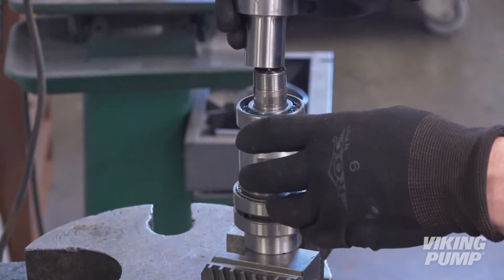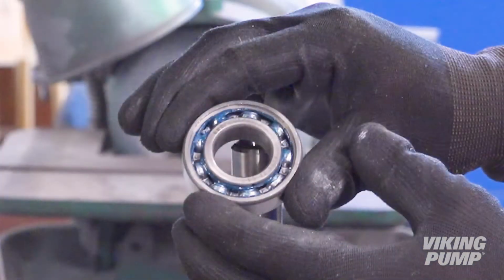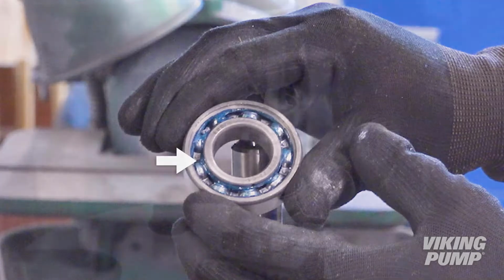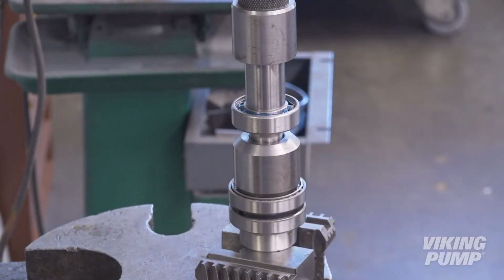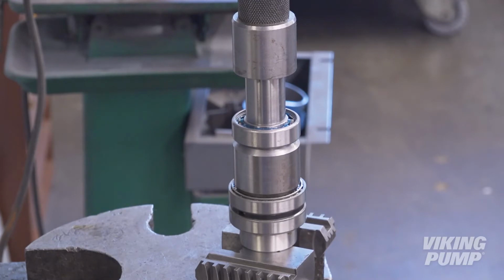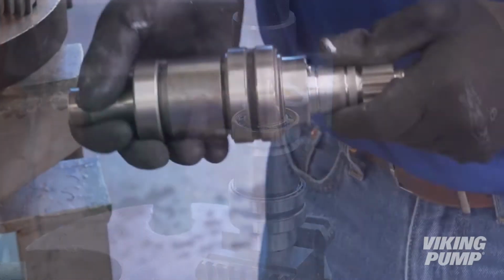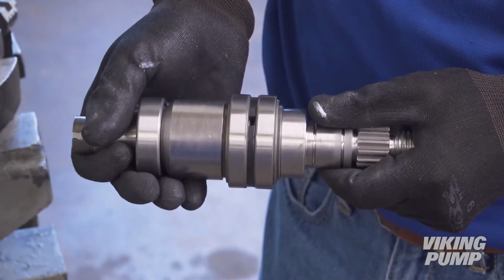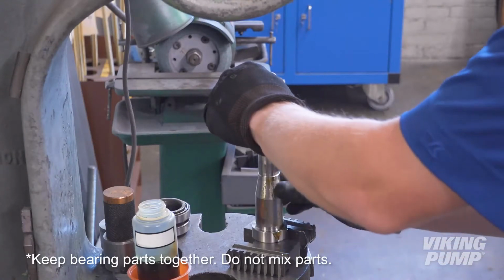Next, lubricate the rear bearing area of the shaft and place the rear bearing over the shaft with the open side up. Using a length of pipe, press against the inner race of the rear bearing until it seats against the spacer. Repeat this process for the other shaft.